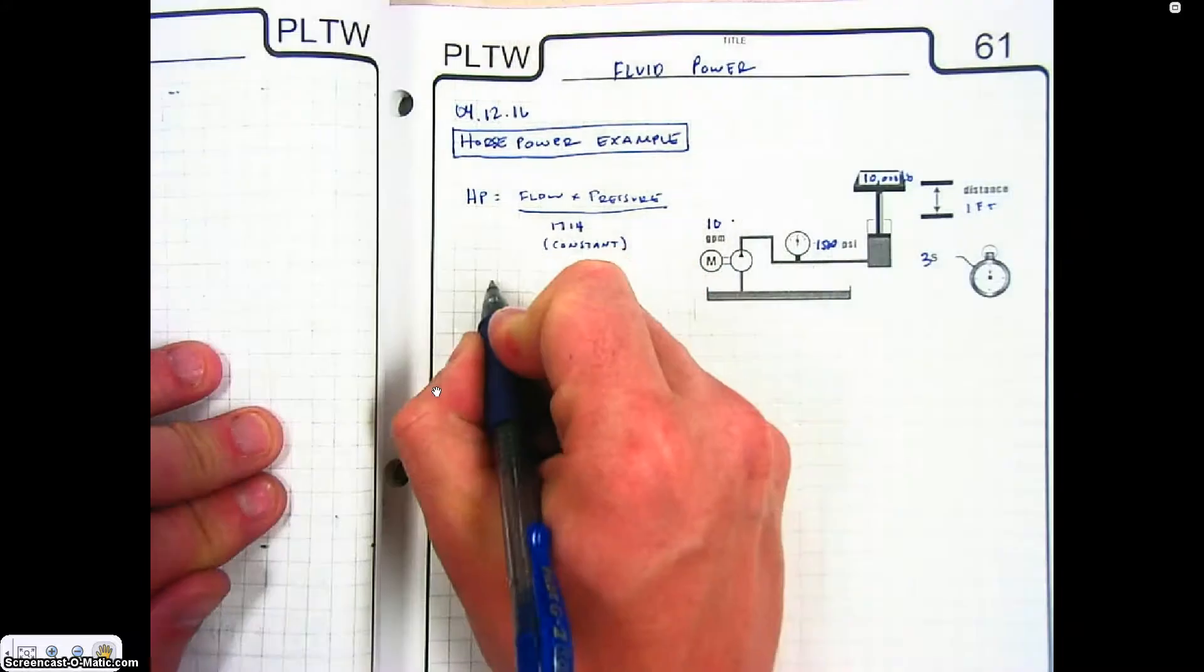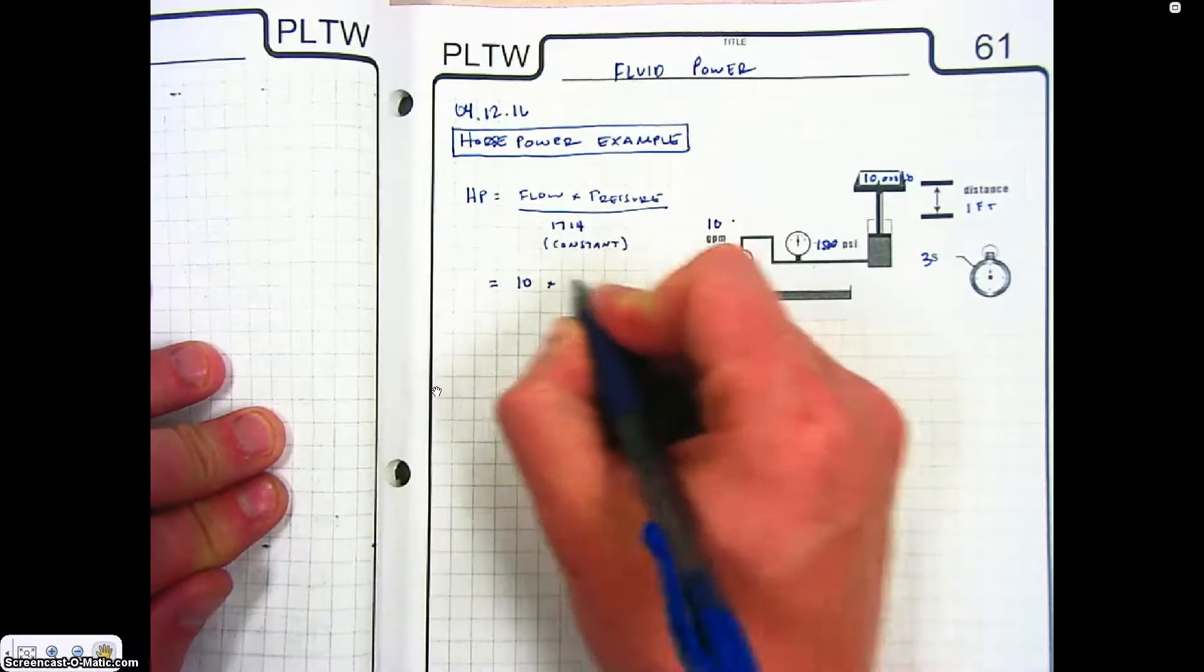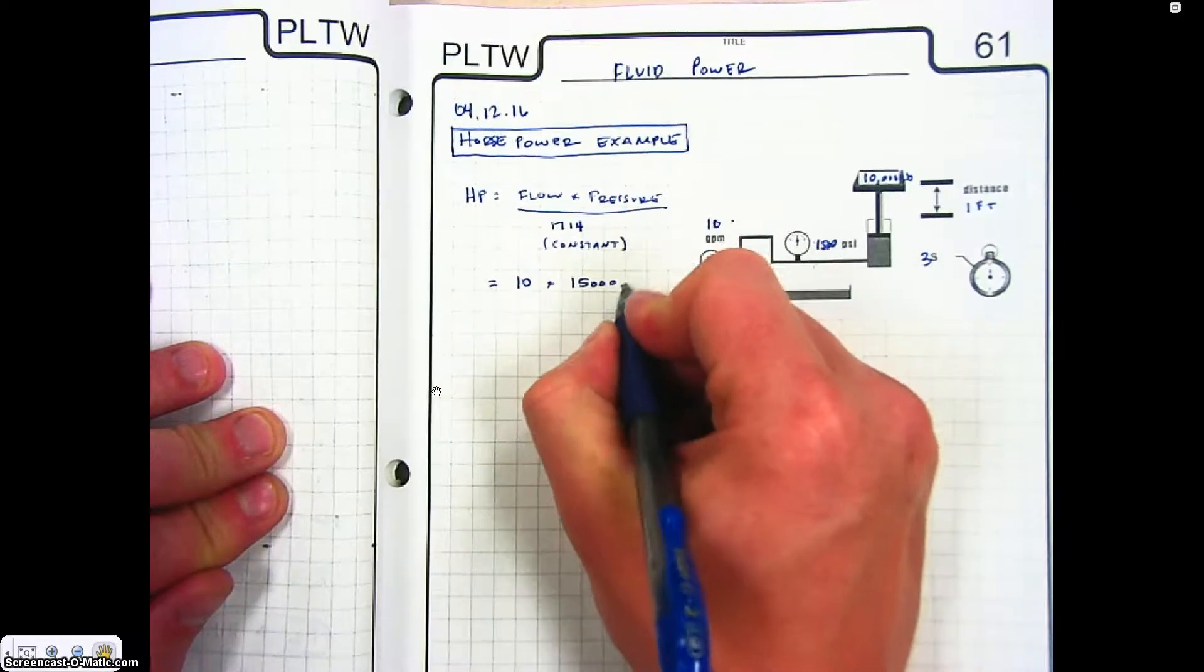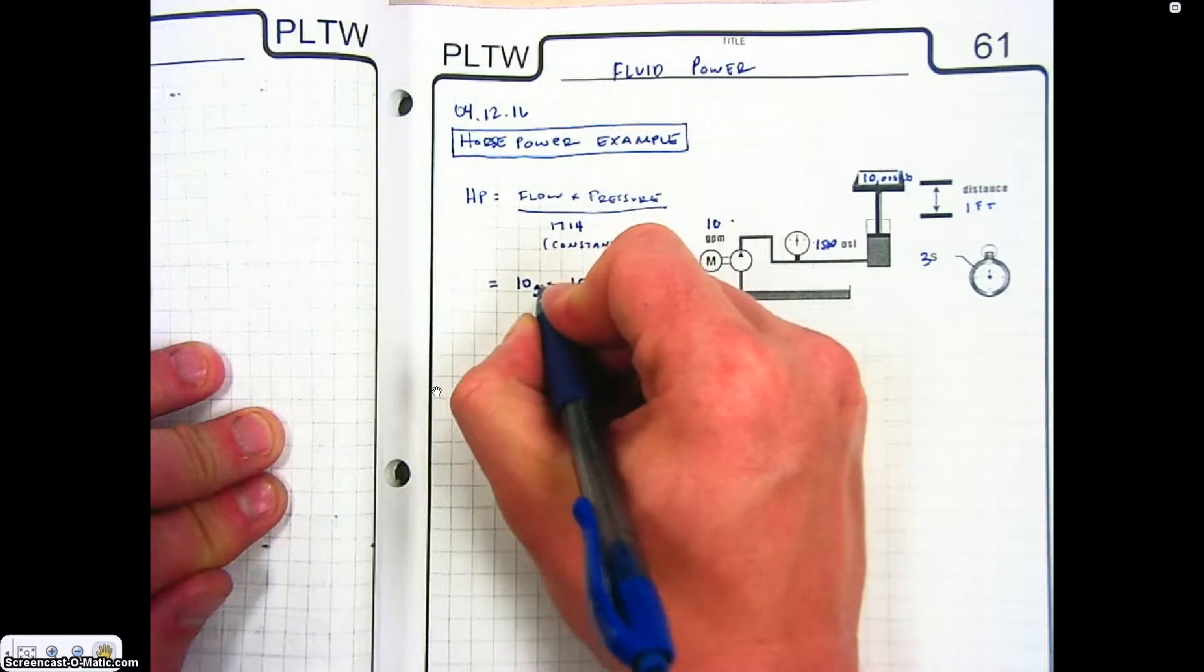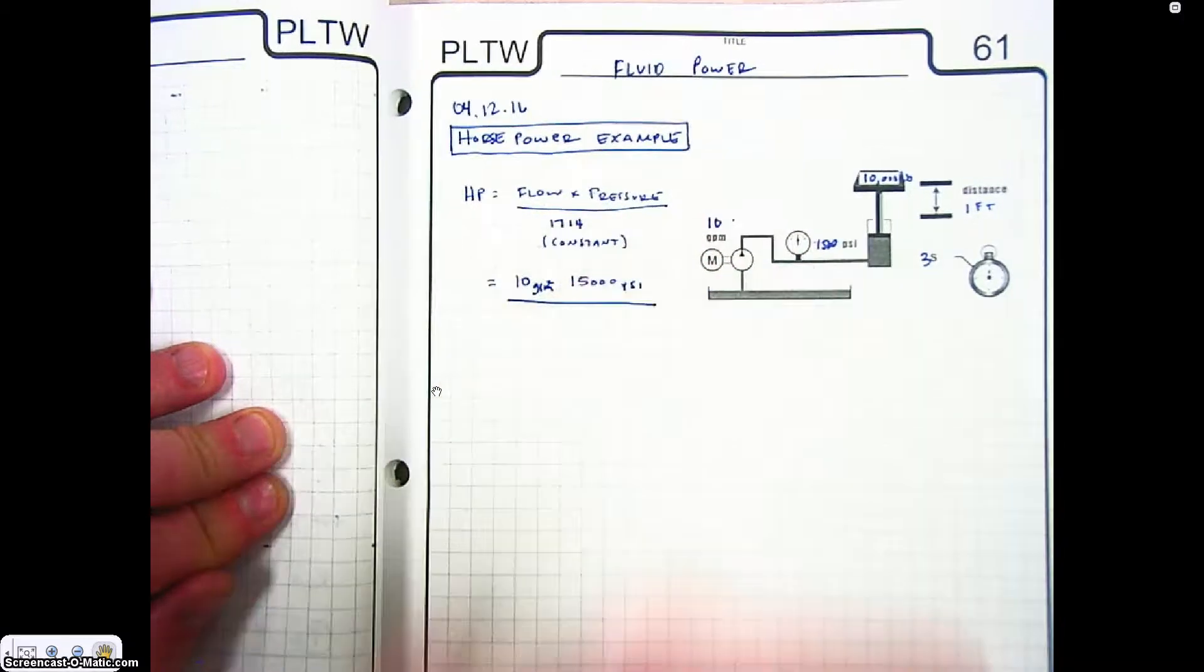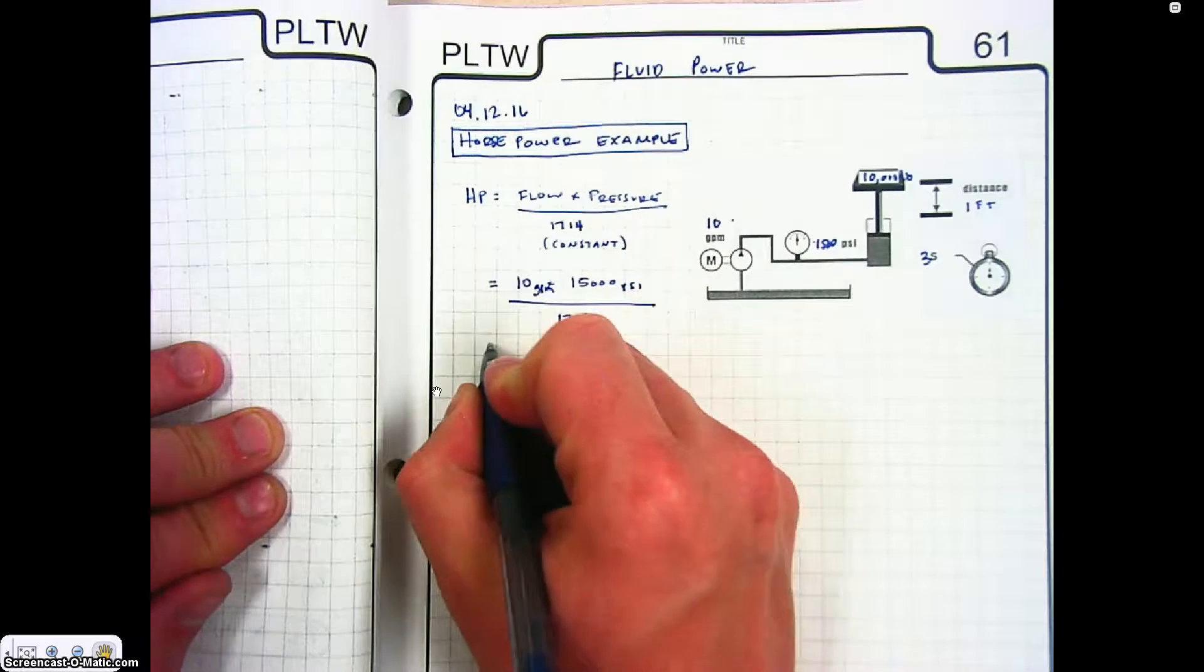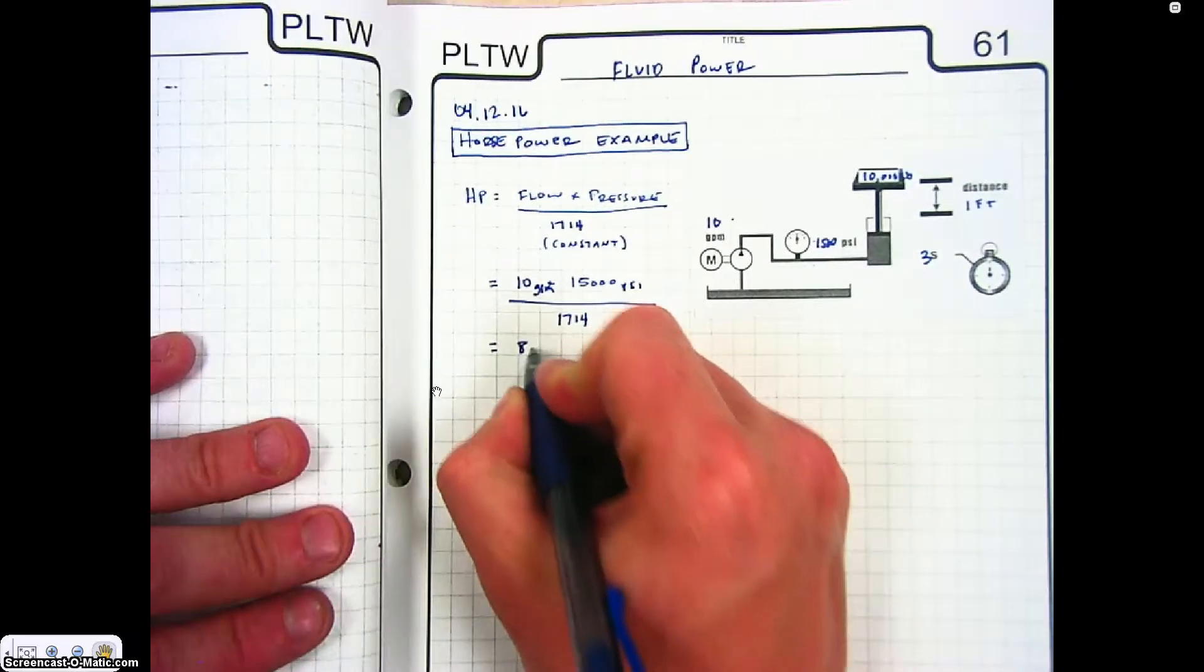And so it's going to be equal to the flow of 10 gallons per minute times the pressure of 1500 PSI, divided by 1714, and we get a horsepower of 8.75.